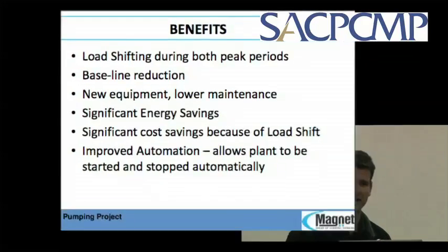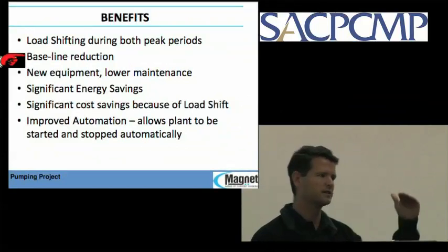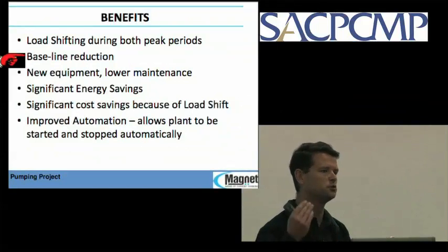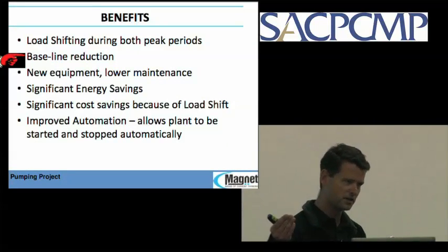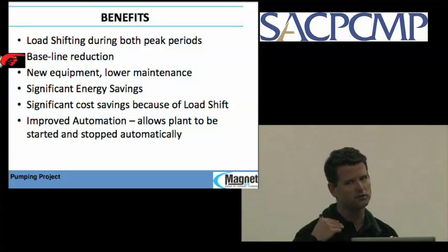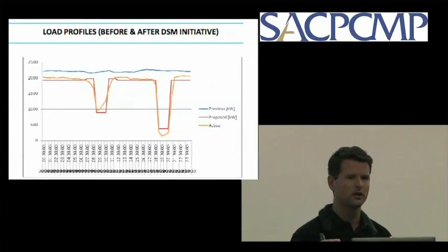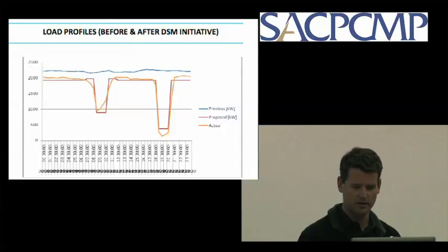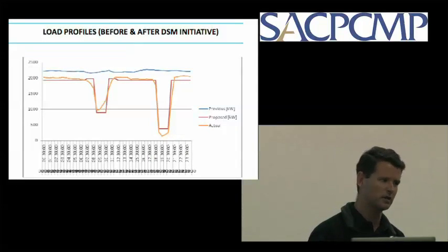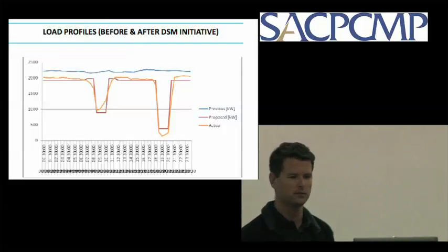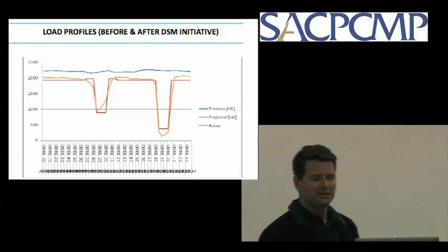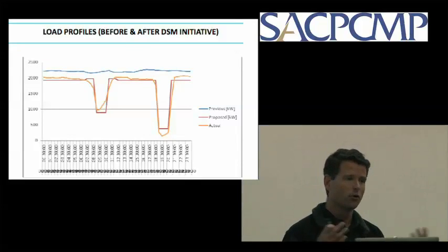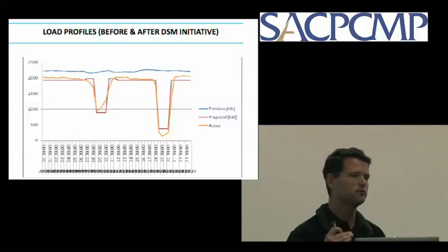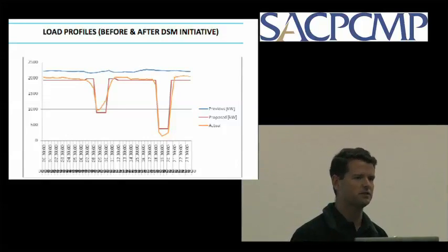There was a baseline reduction. That was one of the reasons Eskom also liked this project. When you do load shifting, you often create a new peak because you're pumping faster once you come back online. But as you could see from that profile, we dropped the overall load of the plant as well as doing load shifting, which created lots of arguments because they were saying, well, we were load clipping and things like that, but we got past that. So there were significant energy savings. Overall, if you just look at the difference between the two profiles, it was about a 25% energy saving.